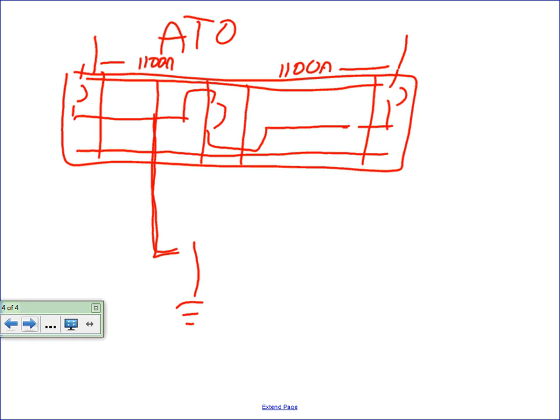Now all of a sudden, or even if you don't have a ground fault, let's say you don't have a ground fault, you have 3,000 amps of neutral current coming back. Without switching that, now you've got 1,500 amps flowing both directions. Well, the system's automatically going to assume you have a ground fault at that point and trip. So we have to design a special ground fault system to accommodate the neutral currents flowing both directions.